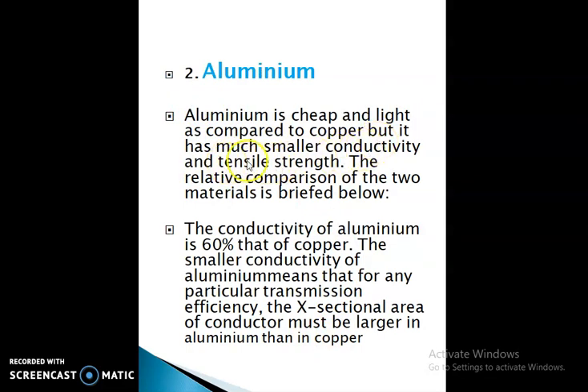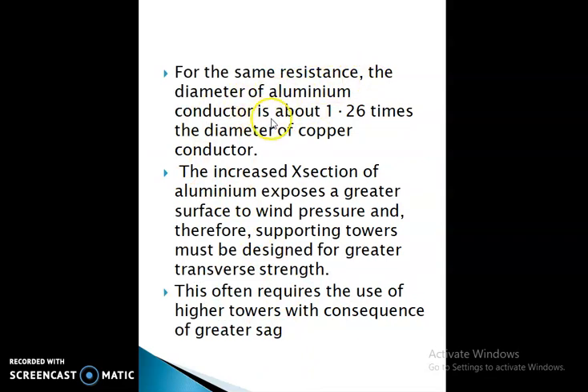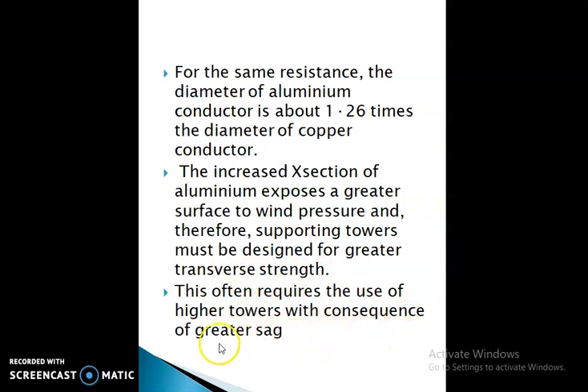The trend is to use aluminum in place of copper. Aluminum is cheap and light compared to copper, but has much smaller conductivity and tensile strength. The conductivity of aluminum is 60 percent that of copper, meaning for any particular transmission efficiency, the cross-sectional area must be larger in aluminum than copper. For the same resistance, the diameter of the aluminum conductor is about 1.26 times the diameter of the copper conductor. The increased cross-section exposes a greater surface to wind pressure, so supporting towers must be designed for greater transverse strength, requiring higher towers with consequent greater sag.